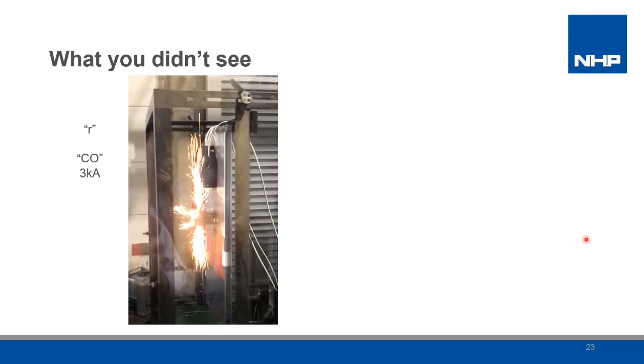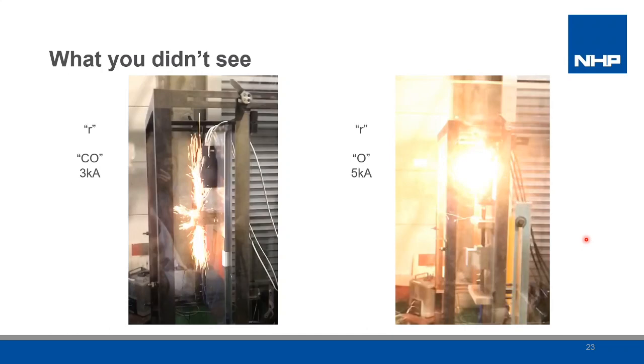The switchboard construction needs to consider this energy. Even at the low fault levels of our tests, the thermal release function is being triggered with the magnetics, and opening time can be slower. This contactor is closing onto a short circuit value of 3 kA with a 100 amp MCCB, whereas this one here is a 250 amp MCCB tripping from a short circuit at 5 kA. So even at panel board level, the energy released as a breaker and contactor interrupt a fault, with the heat and pressure, can cause doors and escutcheons to be blown open if not properly secured.